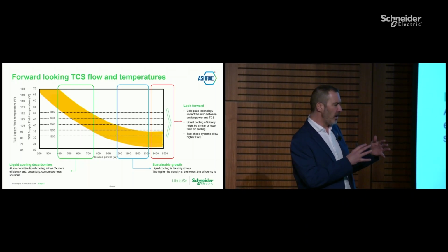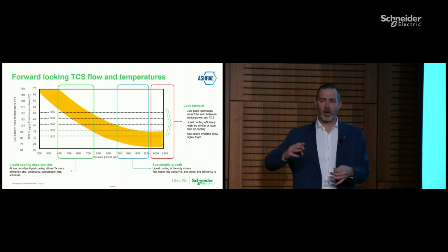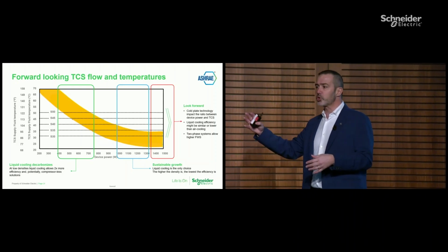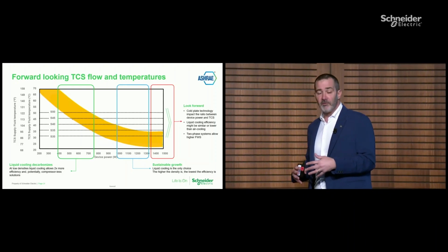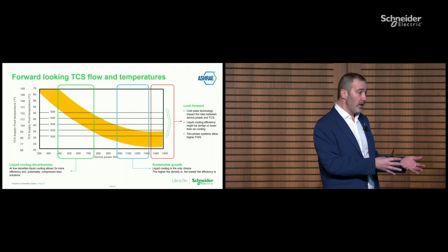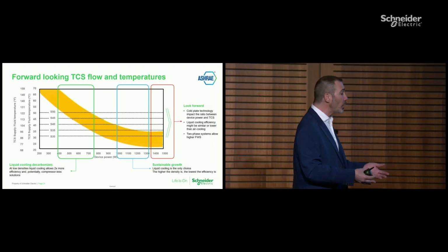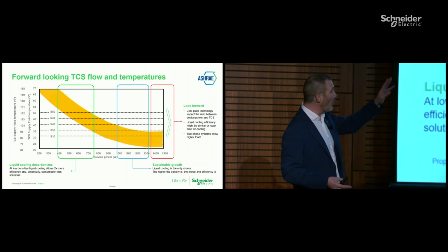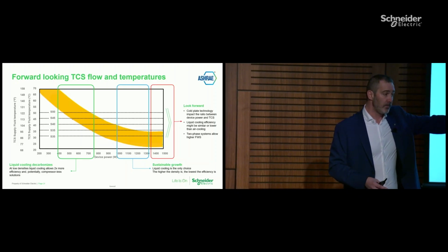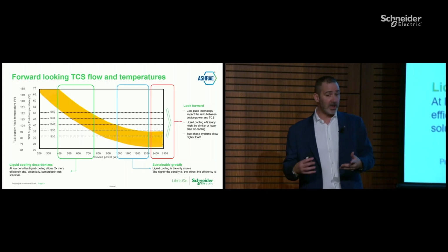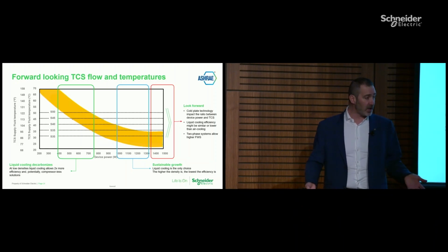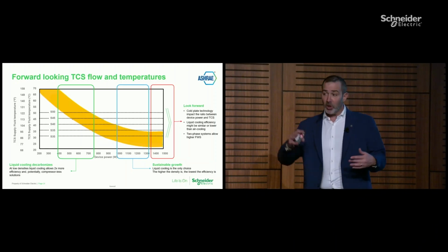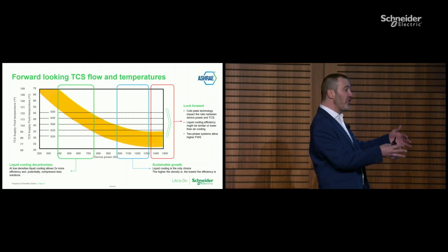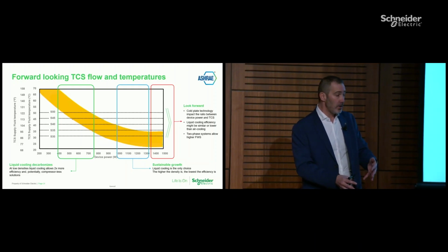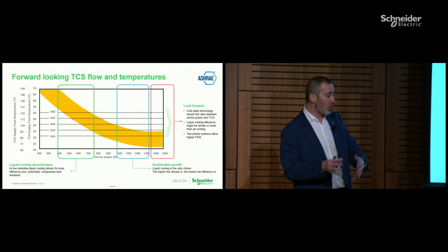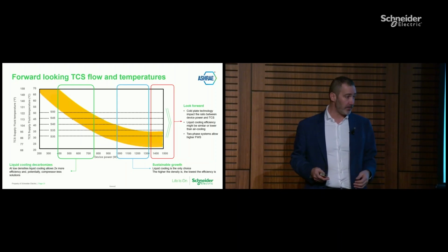That's clearly something that in the long run is not sustainable. So very likely, either we find a better way to exchange heat with better cold plates, or when we're in the red area, something new will come, like two-phase direct-to-chip or other technologies. Simply because it's not sustainable - we don't have the power to provide cooling at such low temperatures.